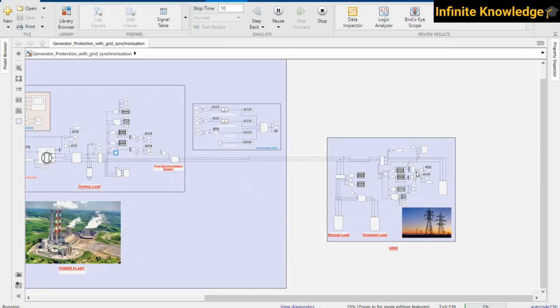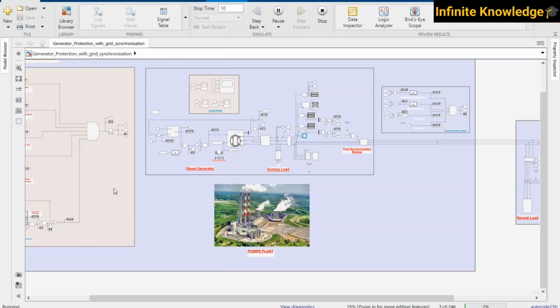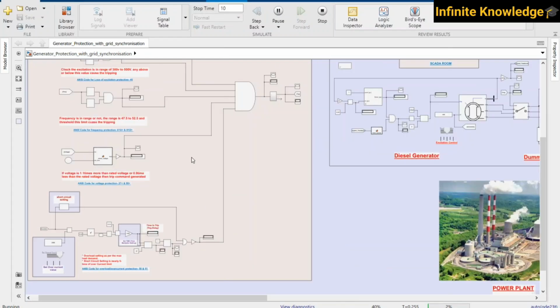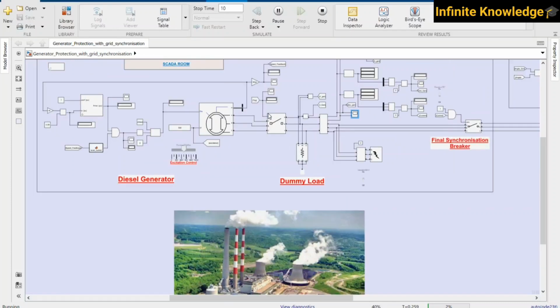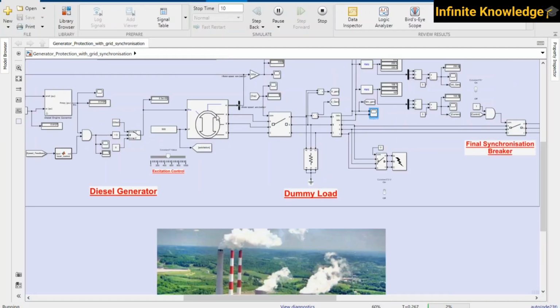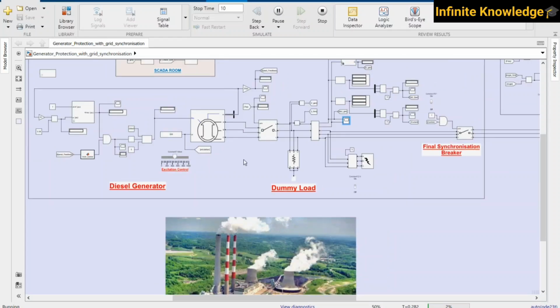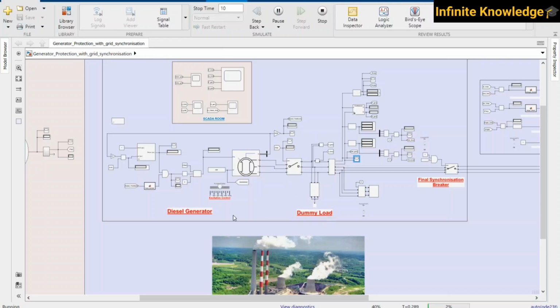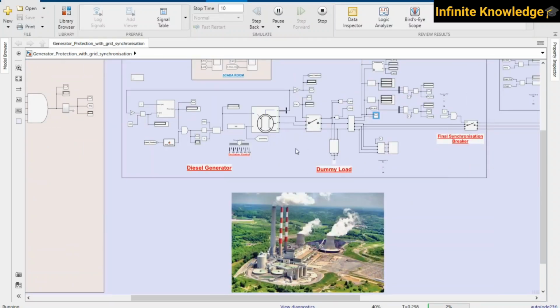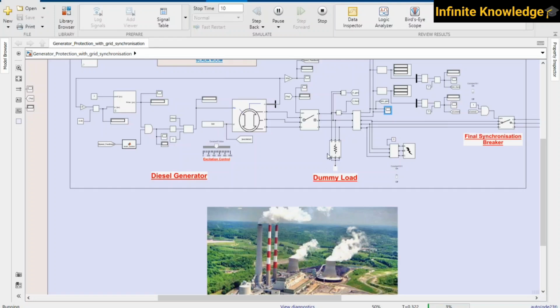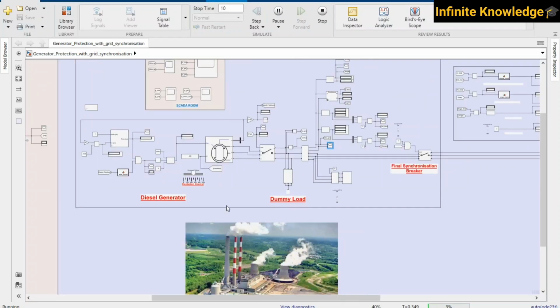And yes, this is a protection circuit. Obviously, if there is any abnormality, then it will detect and it will isolate this breaker. The breaker which is recently connected, directly connected at the terminal of the generator, totally isolates the generator from our grid or even a dummy load. Okay, what is a dummy load? Dummy load is the auxiliary load. When you are running the power plant, to run the power plant itself requires some power source. So that is known as a dummy load or critical load, I can say, and that may be 10 to 12 percent of the entire generation, depending on the size of the power plant.